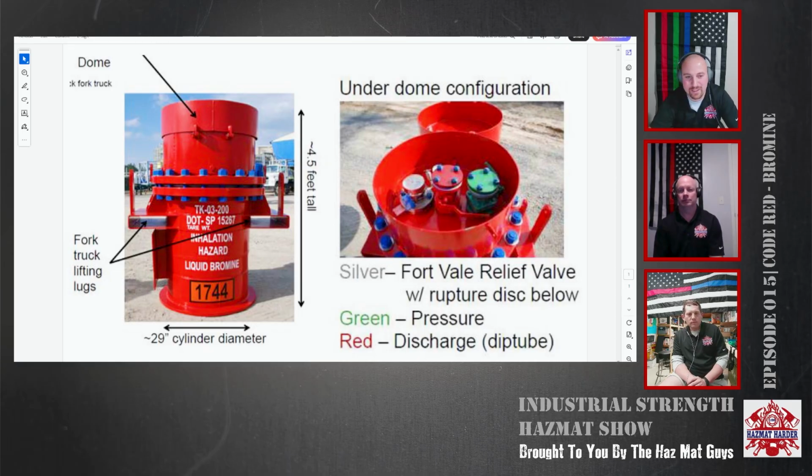Yeah. But due to DOT regulations, like we talked about with the corrosiveness of these, they deem those containers unsafe to travel by road, especially in the quantities that large manufacturing facilities like ours need. So they swapped over these containers. Right. So now we use these, which the picture on the right shows are under the dome configuration, more of a top-up look, if you'll say. You actually have 2 flange connections with isolation quarter-turn valves underneath that you hook dedicated lines and flanges up to, and on the left there's actually a built-in relief valve in case it does overpressurize in transportation.